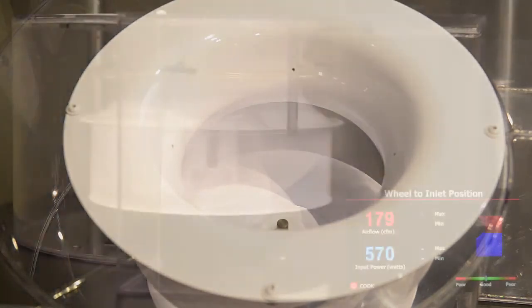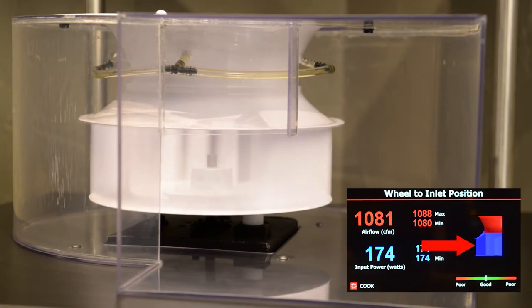We start out with the wheel in the ideal position, overlapping the inlet as detailed in the installation and operation manual. During this demonstration, the wheel speed will remain constant. The display screen shows the wheel in blue and the overlapping inlet in red. You can see the airflow is approximately 1080 CFM and the power consumption is 174 watts.